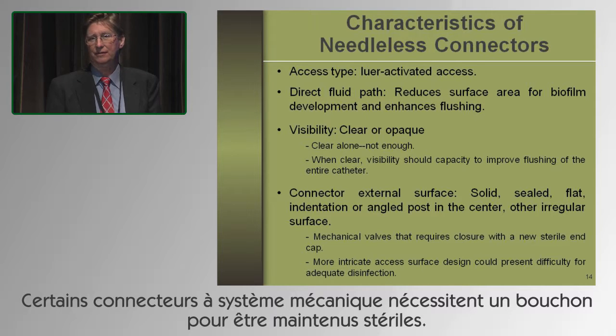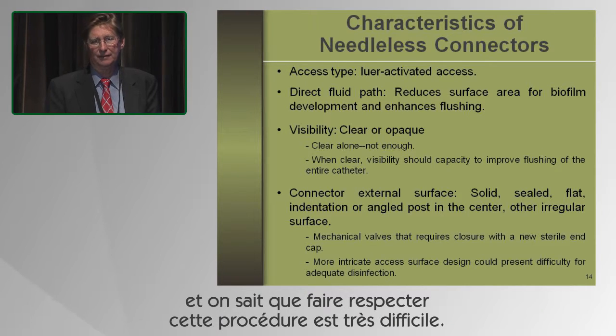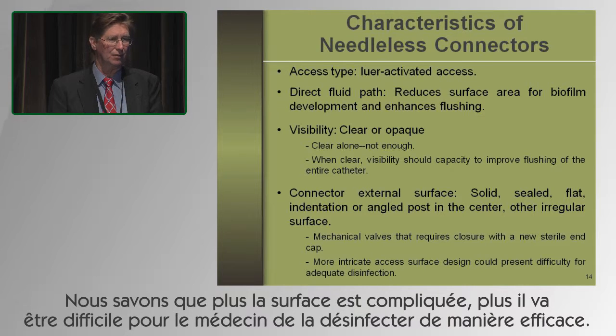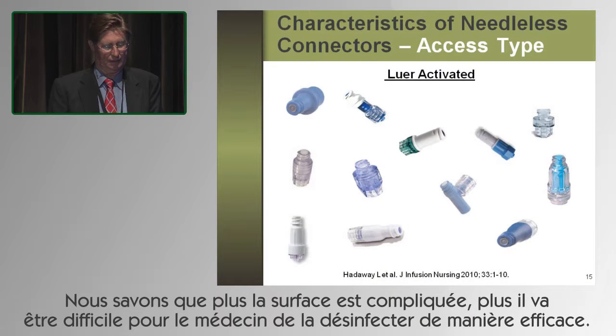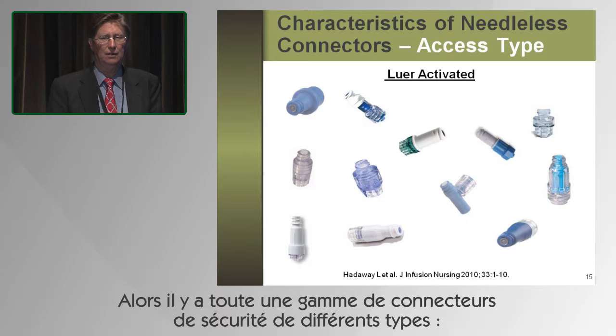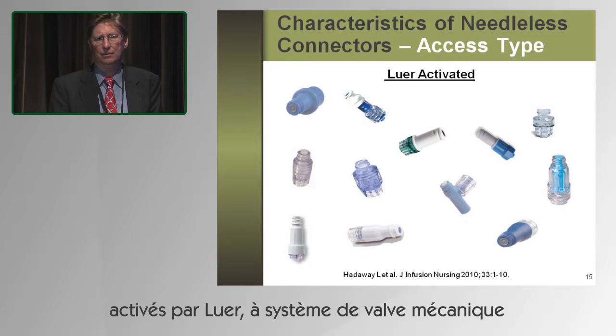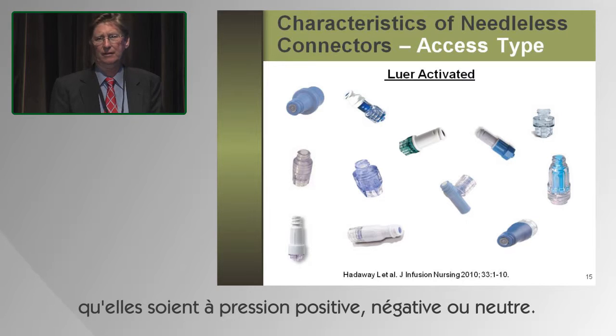Some of the mechanical valves have required end caps to keep them sterile, and getting compliance with putting those caps on is very difficult. And we know that the more intricate the access surface, the more difficulty it is for clinicians to adequately disinfect them. If we look, there's a wide variety now of luer-activated mechanical valve needleless connectors, whether they be positive, negative, or neutral pressure.